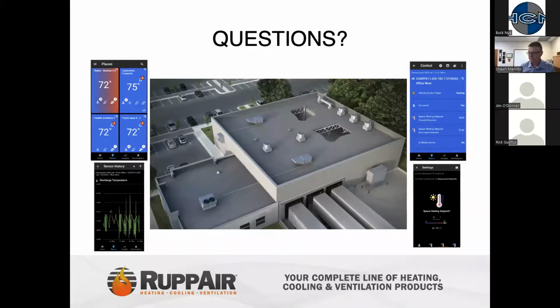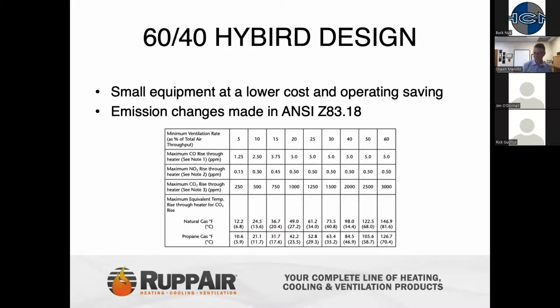Okay. Next question is sort of a mouthful. For the ANSI chart shown for the carbon monoxide based on percentage of outside air, does this assume quote clean outside air? For these warehouses, there may be adjacent warehouses, or the rooftop HVAC units may be adjacent to the loading dock area where byproducts of exhaust are present from trucks and vehicles. I assume that consideration needs to be given to these factors, just like infiltration through loading dock doors with prevailing wind direction. It absolutely does. Basically the question states that this is considering you have good, clean, fresh air. So in the design of these makeup air, fresh air introduction systems, make sure you are away from exhaust points within the building and not near vehicle emissions. So yes, that's a fair statement.